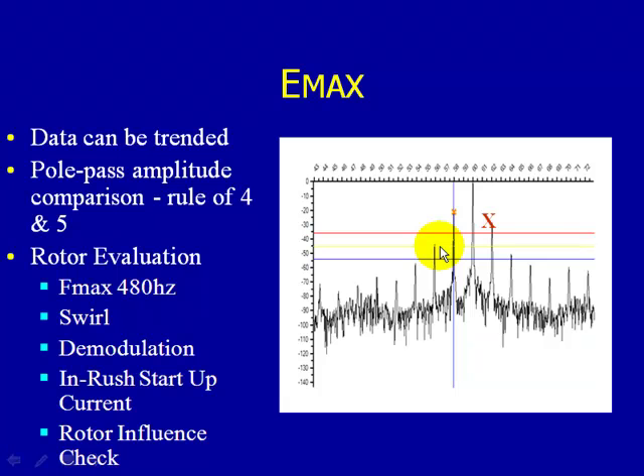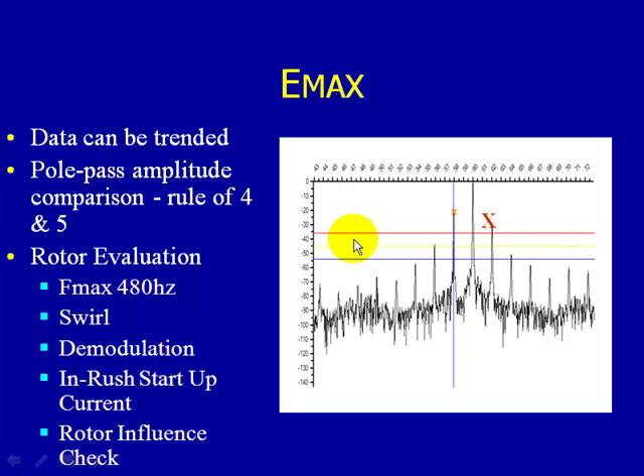PDMA, as you can see here with our E-MAX, uses a spectral analysis approach. Spectral analysis allows us to take a simple current signal and apply an FFT, or fast Fourier transform, algorithm. FFT capability reveals small but very informative frequencies, like pole pass frequency. Here we have an X on our pole pass frequency, and you can see PDMA puts in our observed line, caution line, and severe line. As the problem gets worse — whether a single cracked bar or multiple cracked bars — you'll see this pole pass frequency develop more energy and stand out from the baseline noise level of the spectrum.